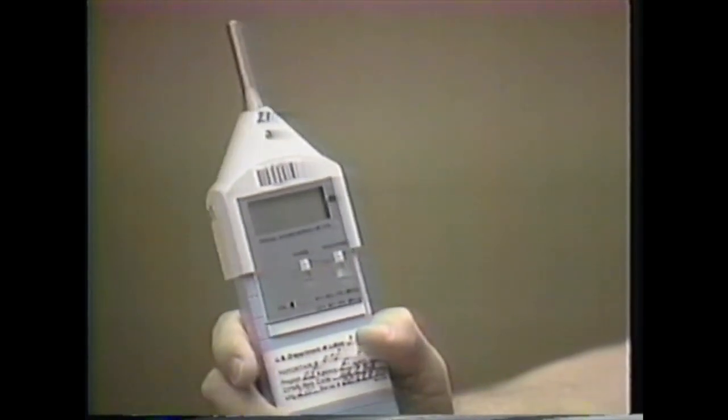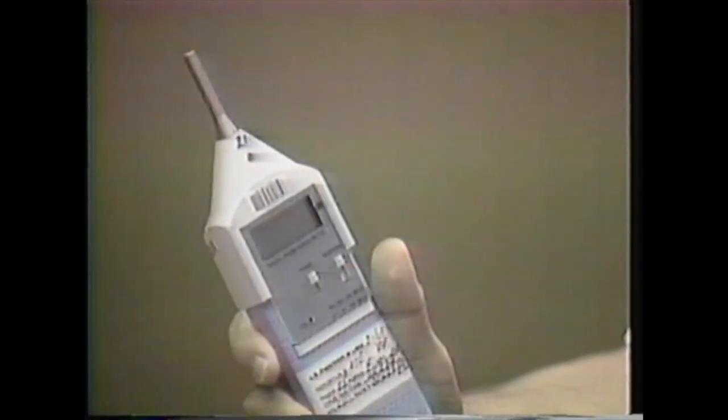Now we'll turn our attention to calibration. First we'll calibrate the type 2 sound level meter, and then we'll calibrate the type 1. In calibrating this instrument, we have 2 different sizes of microphones. In order to ensure a snug fit between the microphone and the calibrator opening, we need to place an adapter in the calibrator opening, which I will now do.